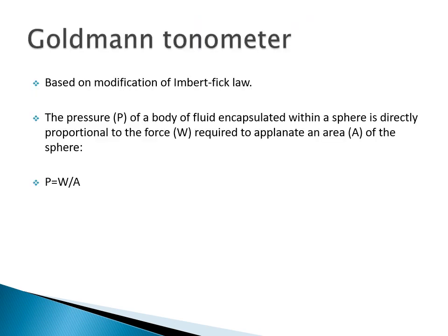Now coming to the Goldmann applanation tonometer. It is based on the modified Imbert-Fick law. The Imbert-Fick principle is that the pressure of a body of fluid encapsulated within a sphere is directly proportional to the force required to applanate an area of the sphere. That is, pressure is equal to force divided by area.